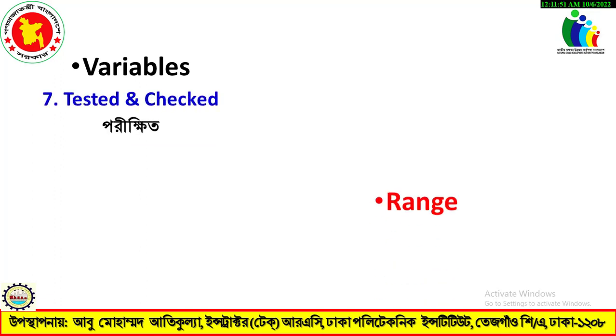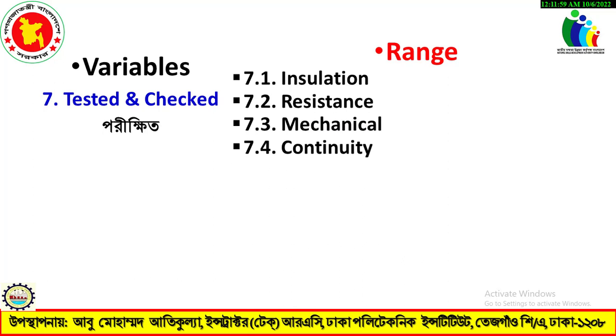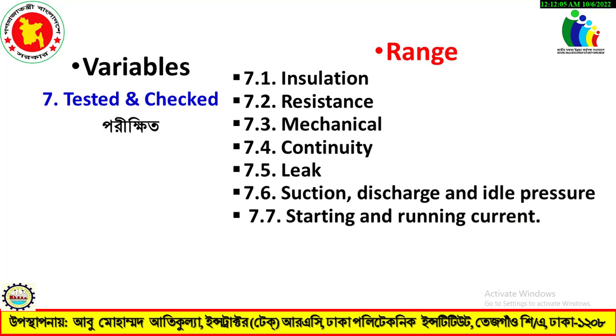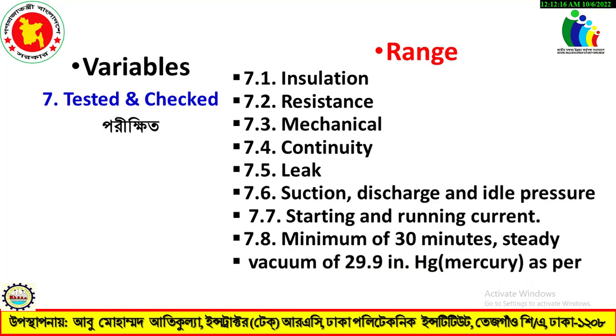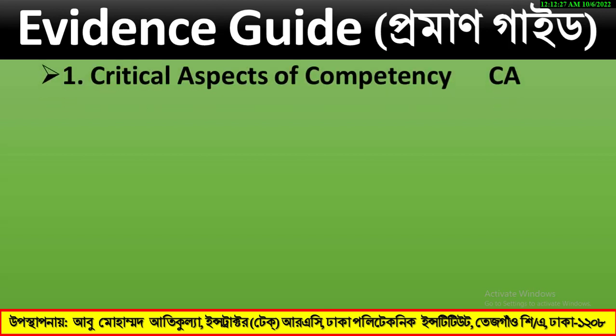Number seven, Tested and Checked: insulation resistance, mechanical continuity, leak, suction discharge and idle pressure, starting and running current, minimum of 30 minutes steady vacuum of 29.9 inches of mercury as per standard.